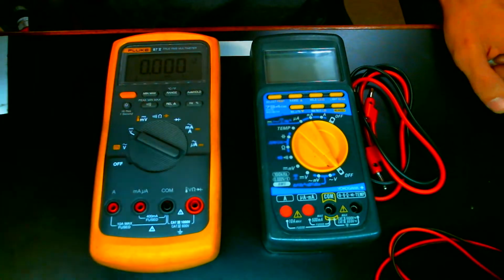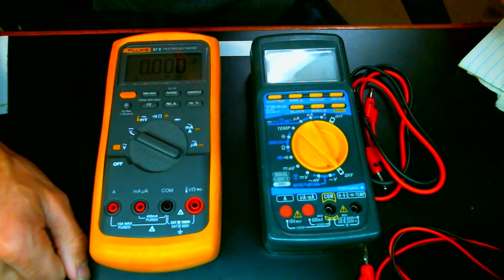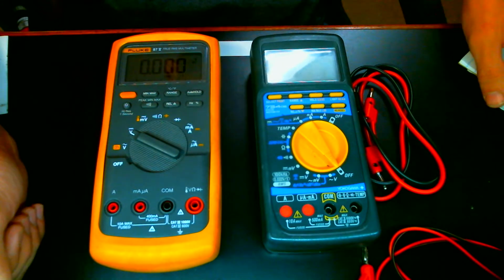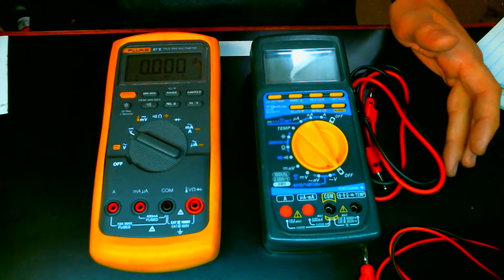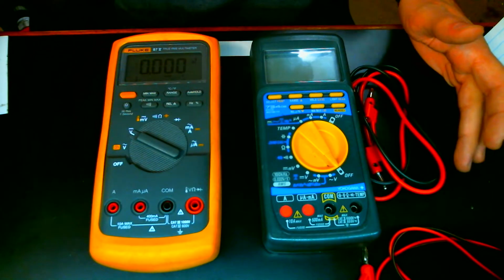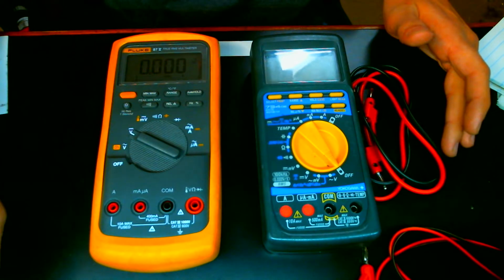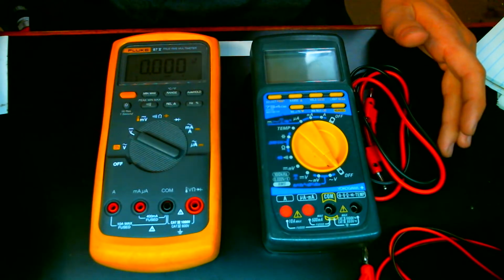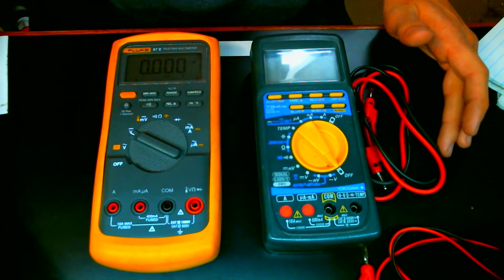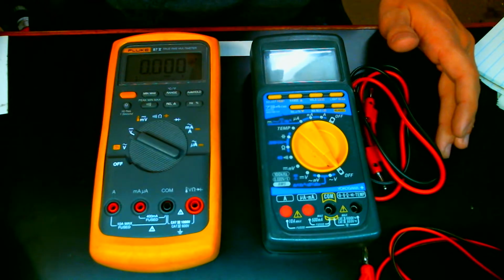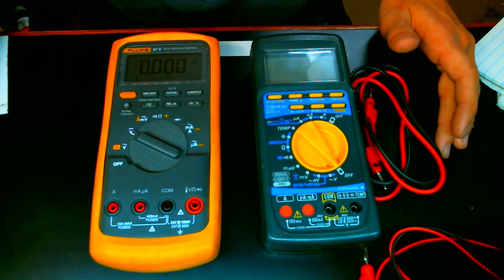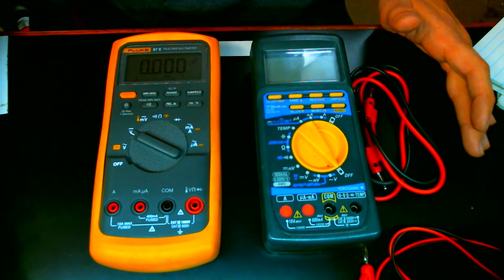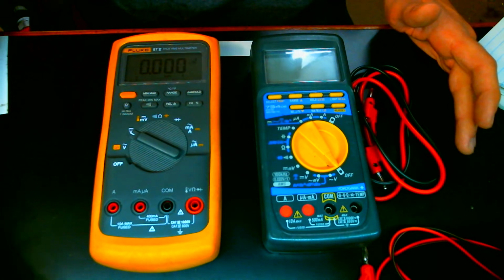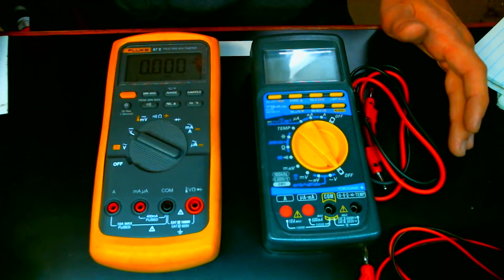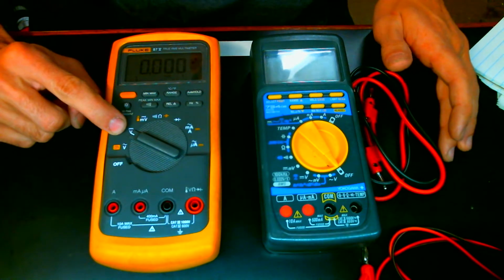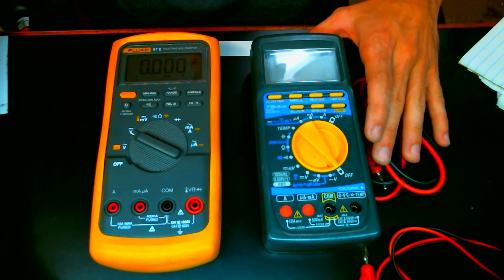So that's pretty much it on the notes on verification, calibration, things like that. As far as what I'm going to do today for verifying, I have a voltage reference source. It's a very old Heathkit. What was his name on YouTube? MJ Lorton. If you check out his channel, he's done a video on this before. It's a good voltage reference. It's only specified to 1% accuracy, which is absolutely horrible for modern meters. But it does provide a very good, stable voltage that I can dial in pretty precisely using the 87 as a reference just to see if we match up. So we'll be using that as our reference today.